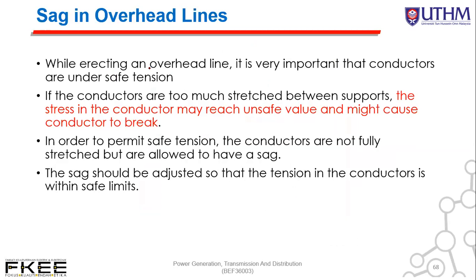Okay, sag in overhead line. While erecting an overhead line, it is very important that conductors are under safe tension. Tak boleh tegang sangat, kan? Tak boleh kendur sangat. Okay, if the conductors are too much stretched between support, the stress in the conductor may reach unsafe value and might cause conductor to break. Kalau tegang sangat pun dia boleh putus kan? Boleh terputus lah, boleh pecah kan?